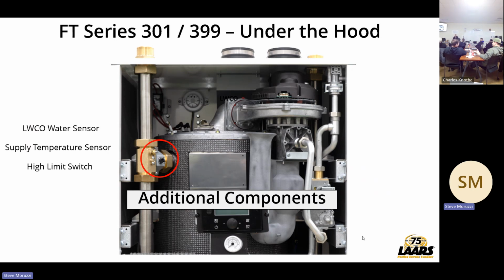If you're in a jam though, with the LTT sensor, you have one of our parts bag kits, the return water sensor for the units, 10K. It doesn't care where it's at, as long as it sees one, it'll let you get the LTT. Yep, so those sensors between LTT or even when you cascade, you have to have a sensor. It's almost like having a rooftop HVAC unit. If you have a thermostat on the wall and someone rips it off, there's nothing telling it what the temperature is and how to control it. So you have to have those sensors installed.